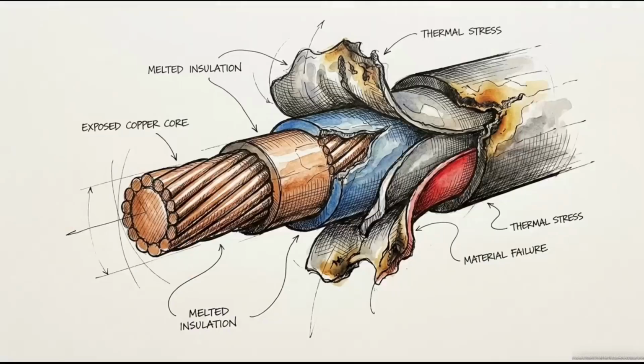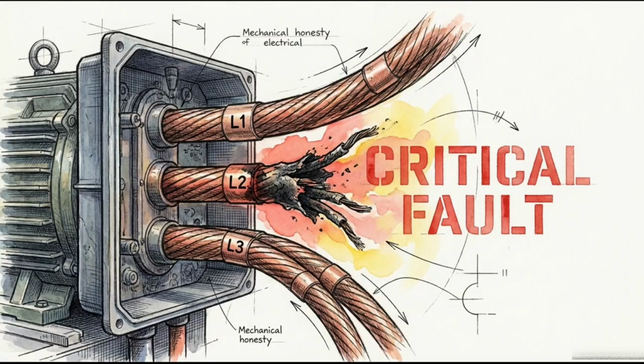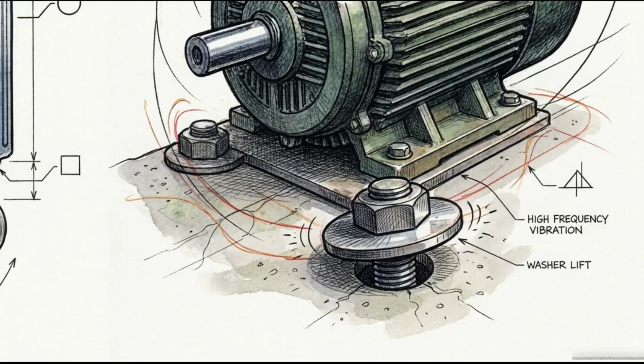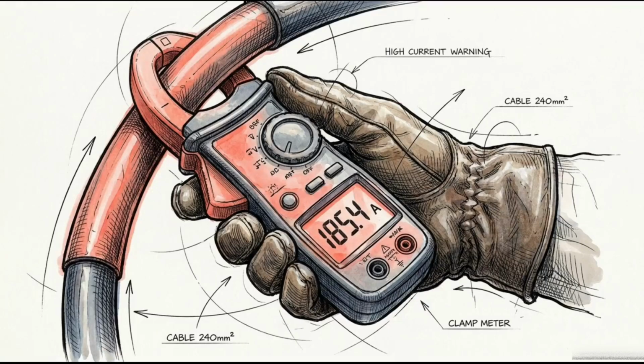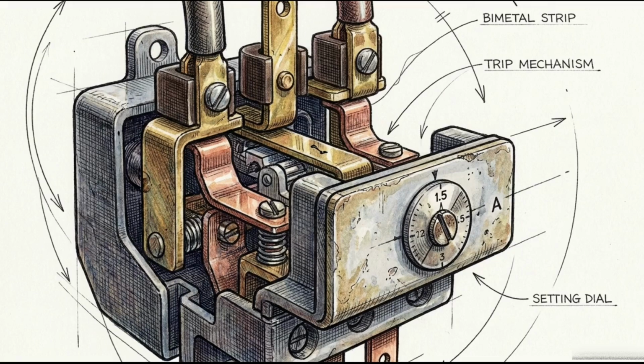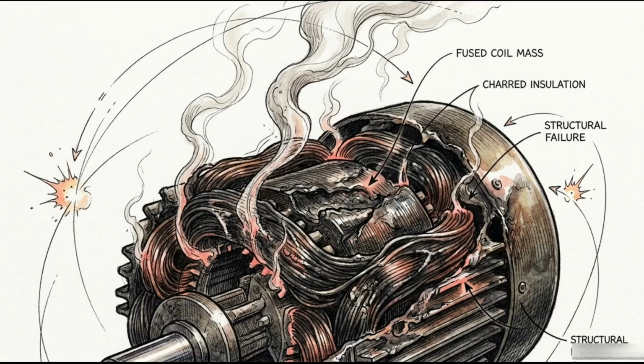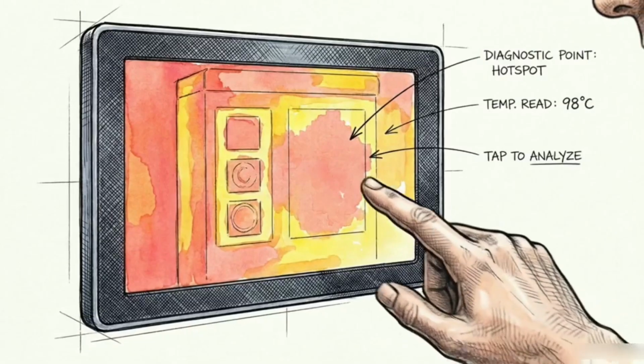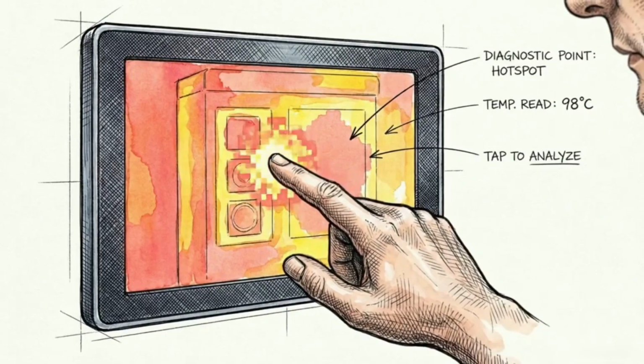Components operating near the 100-degree threshold are in a state of imminent failure. The heat will melt cable insulation and lead to a localized short circuit. One common result of a burnt terminal is single-phasing, a scenario where one of the three power phases to a motor is completely severed. A motor that loses a phase will emit a violent acoustic hum. To compensate for the loss, the motor pulls an imbalanced, excessive current through the two remaining phases. Because standard overload relays are often too slow to react to this specific imbalance, a motor can incinerate its internal windings in under 3 minutes. Using thermal signatures to predict this failure is the only truly reliable way to prevent total motor destruction.